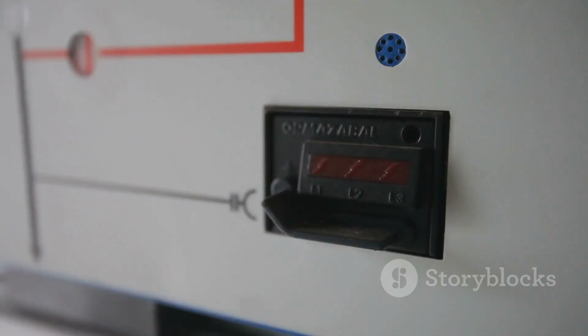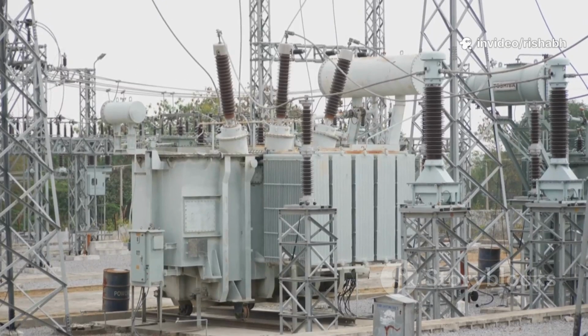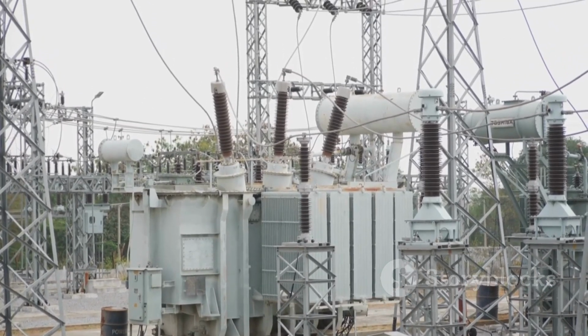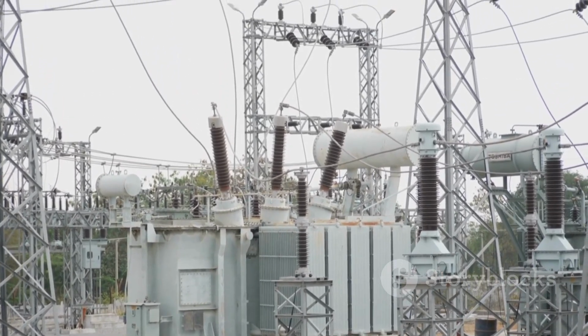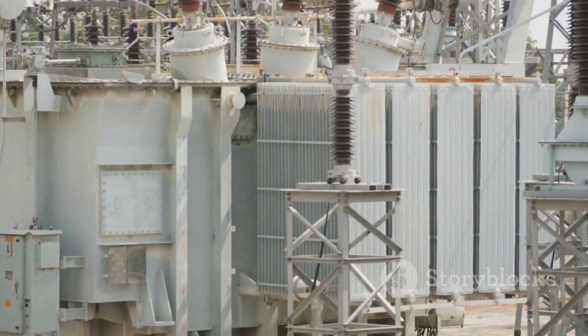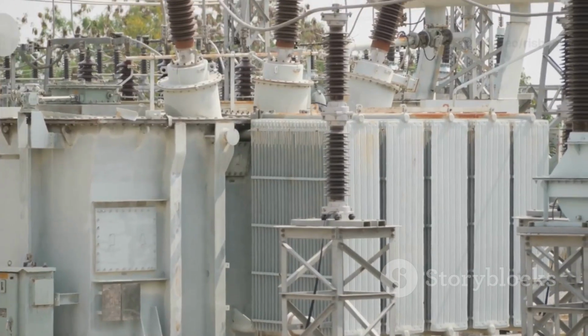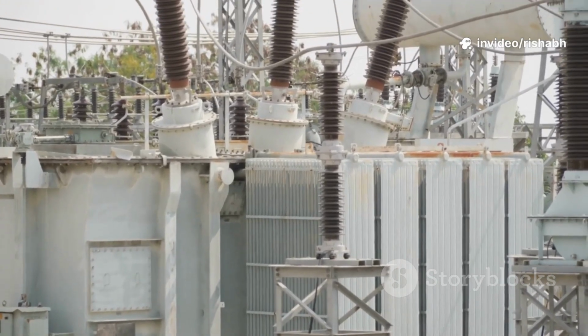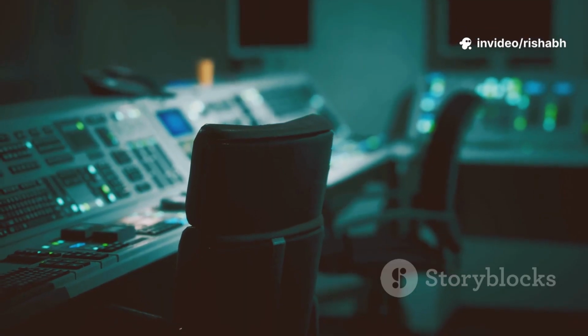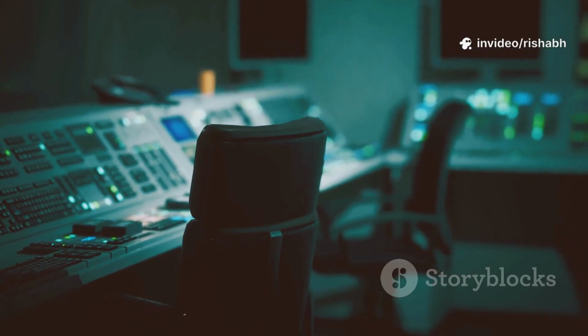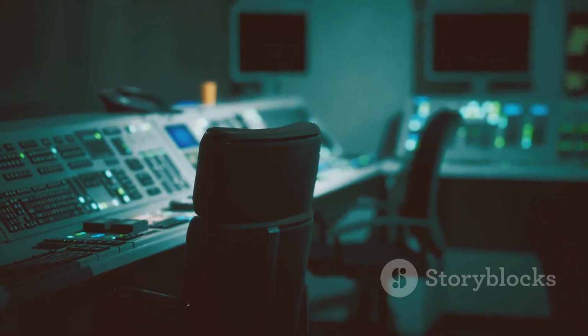If it detects something dangerous, like a sudden surge of electricity or an internal fault, it acts in a fraction of a second. Its main purpose isn't just to sound an alarm, it's to instantly disconnect the transformer from the power grid, preventing catastrophic damage, fires, or widespread power outages. It's a truly remarkable piece of engineering, working silently in the background to keep our world powered.